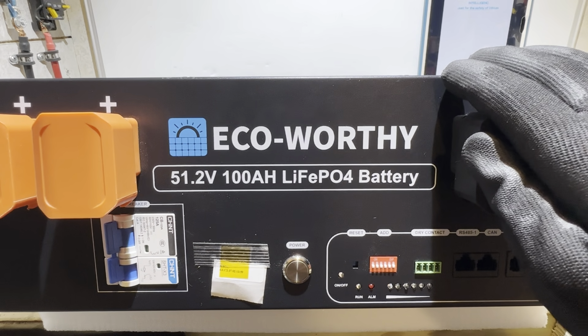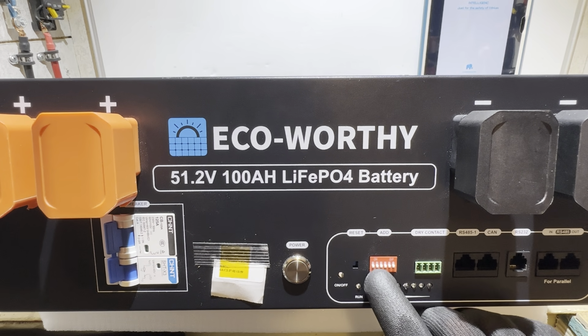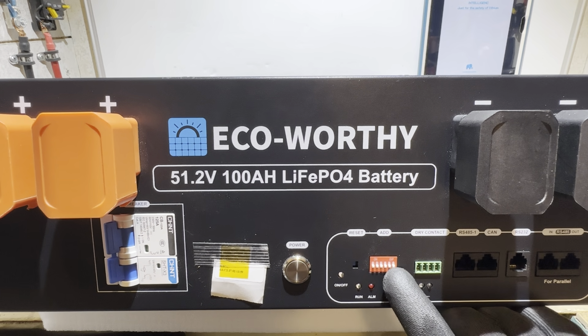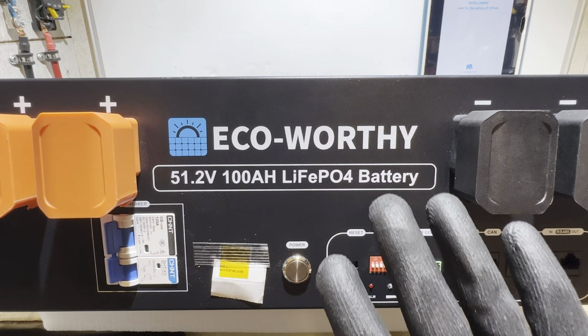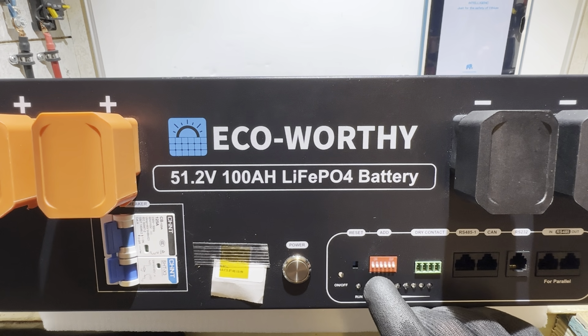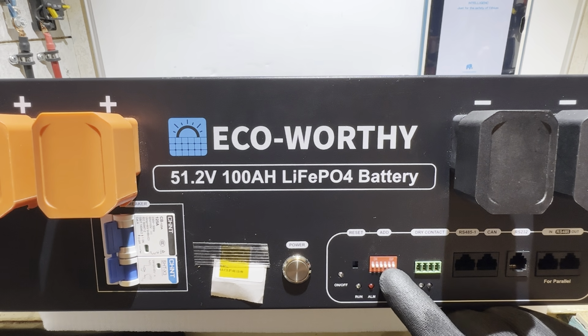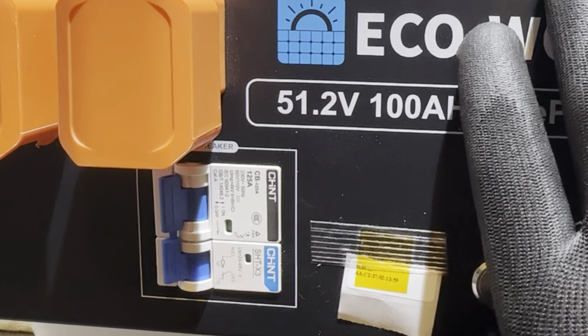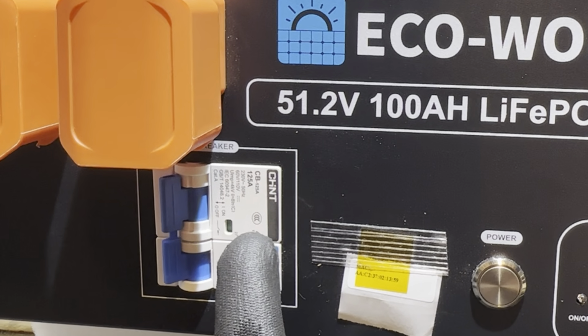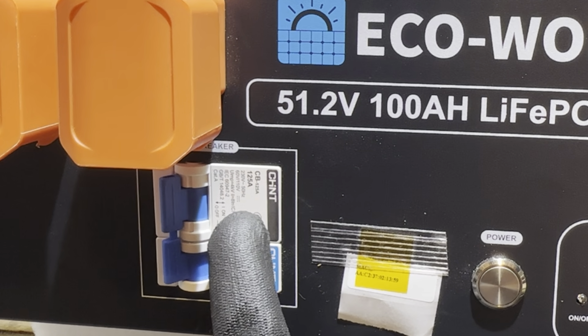This version 3 battery also allows up to 32 batteries in parallel. We have 6 address dip switches versus the 4 on version 2, and version 2 only allowed 15 batteries in parallel. Version 3 also comes with the 125 amp breaker similar to version 2, but this one also has a shunt trip breaker built in for additional safety.